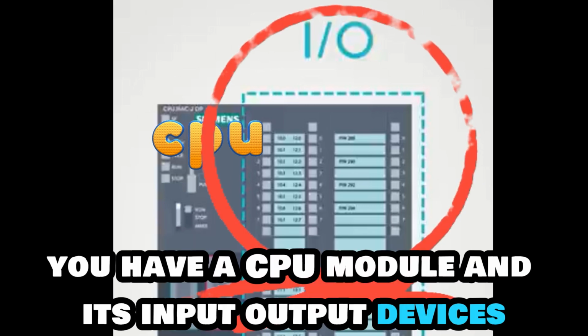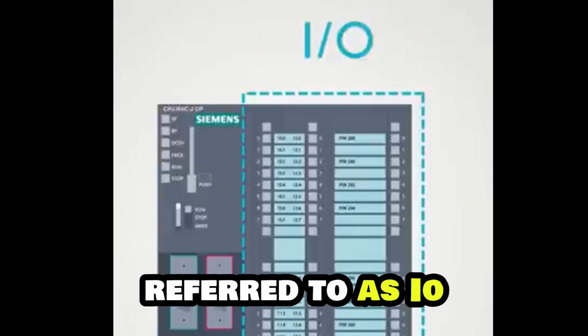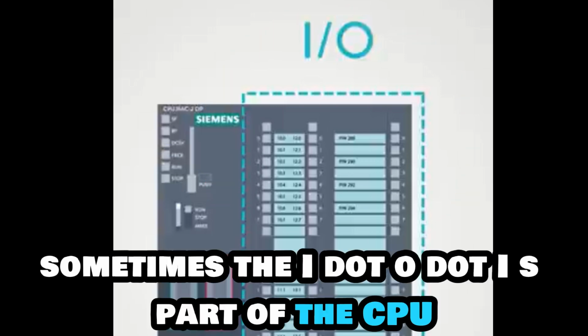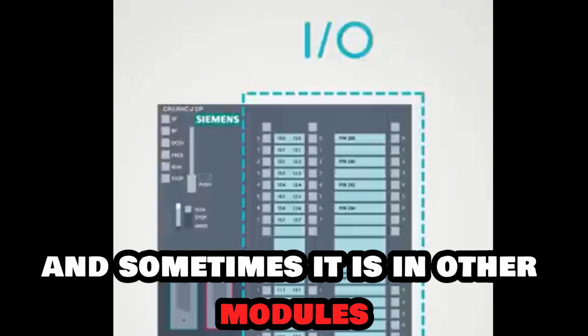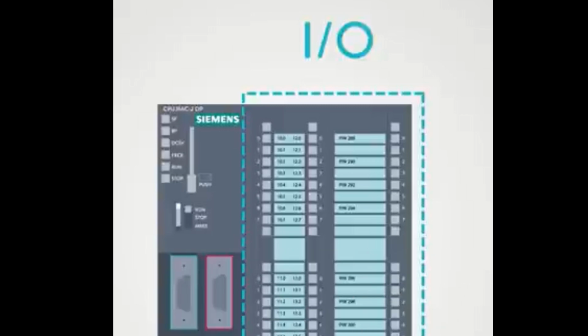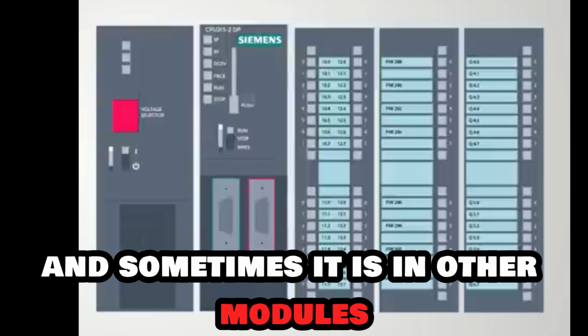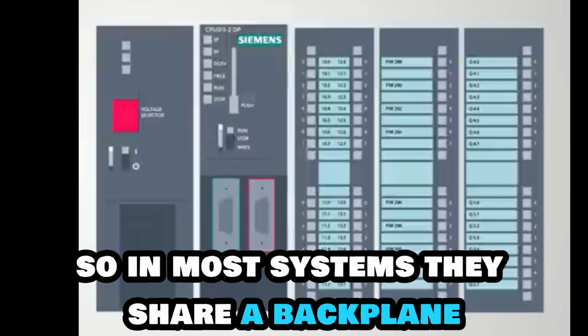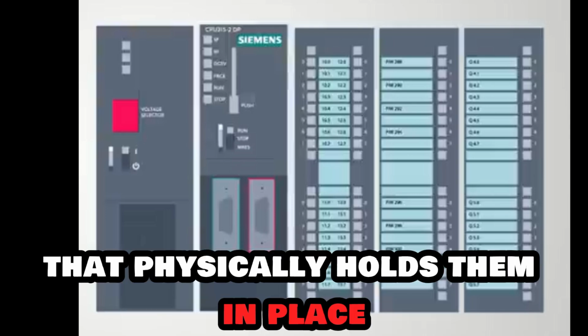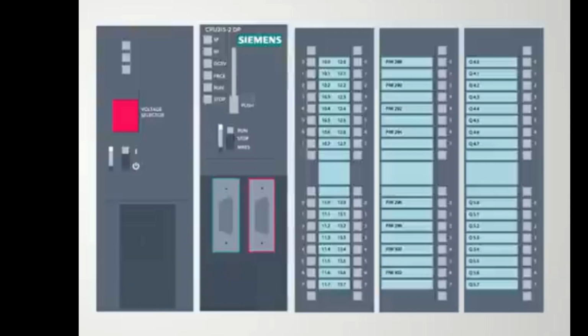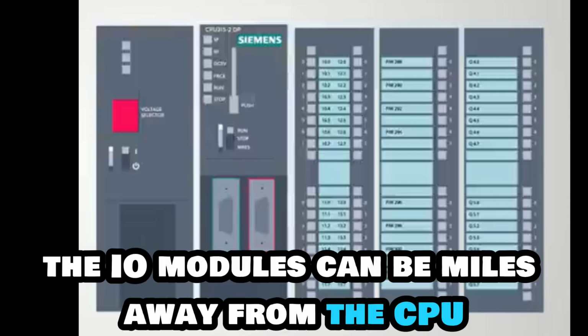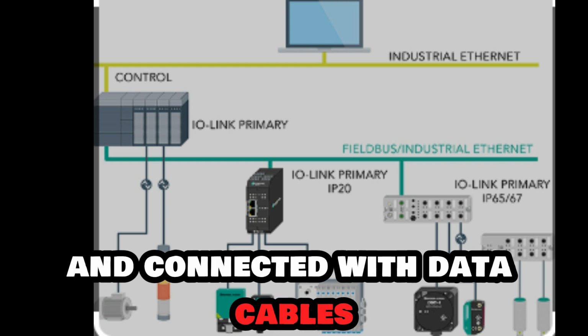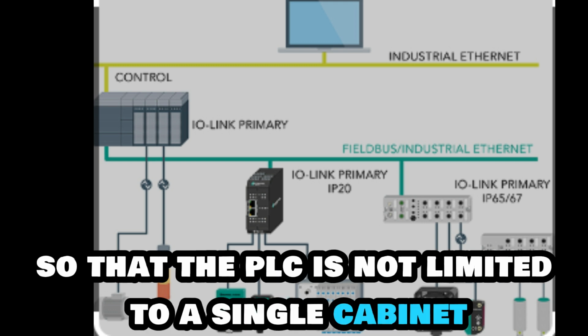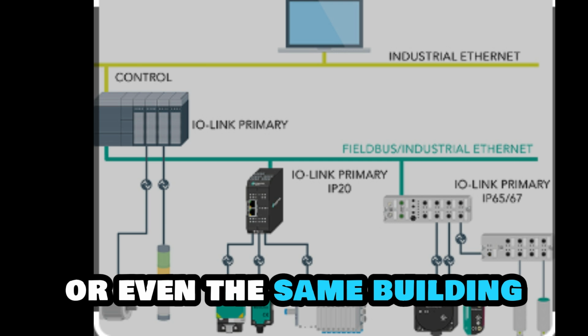An installed PLC is deceptively simple in appearance. You have a CPU module and its input-output devices referred to as I/O. Sometimes the I/O is part of the CPU, and sometimes it is in other modules. In most systems, they share a backplane that physically holds them in place and electronically connects them. In other equipment, the I/O modules can be miles away from the CPU and connected with data cables, so that the PLC is not limited to a single cabinet or even the same building.